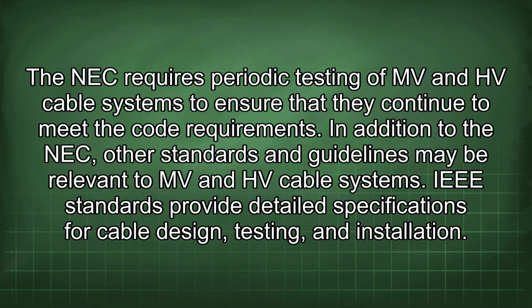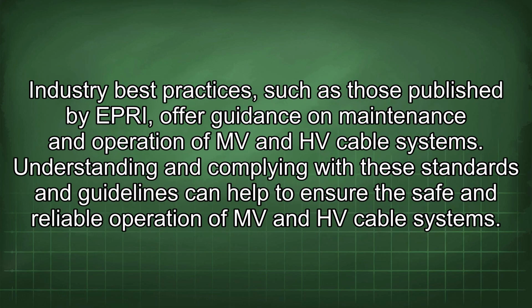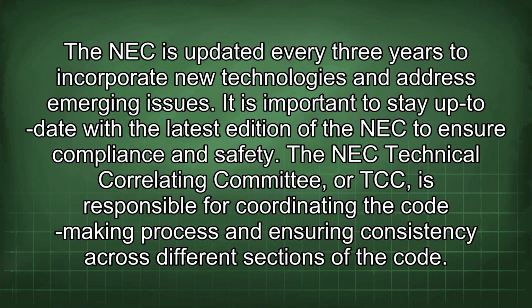In addition to the NEC, other standards and guidelines may be relevant to MV and HV cable systems. IEEE standards provide detailed specifications for cable design, testing, and installation. Industry best practices, such as those published by EPRI, offer guidance on maintenance and operation of MV and HV cable systems. Understanding and complying with these standards and guidelines can help to ensure the safe and reliable operation of MV and HV cable systems. The NEC is updated every 3 years to incorporate new technologies and address emerging issues. It is important to stay up to date with the latest edition of the NEC to ensure compliance and safety.